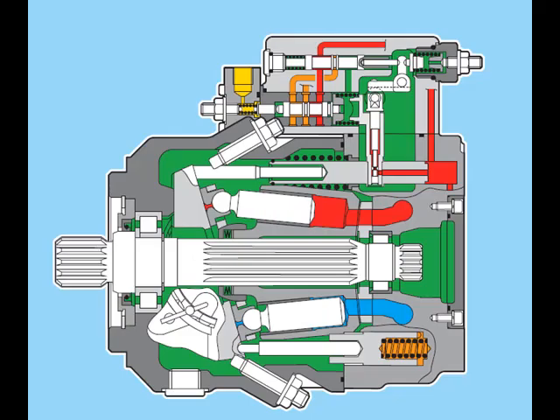LRD Power Control with Pressure Cut-Off. The pressure cut-off corresponds to a pressure control which adjusts the pump displacement back to VG-min when the pressure setting is reached. This function overrides the power control; below the preset pressure value, the power function is effective. The pressure cut-off function is integrated into the pump control module and is preset to a specified value at the factory. Setting range: 50 to 350 bar.